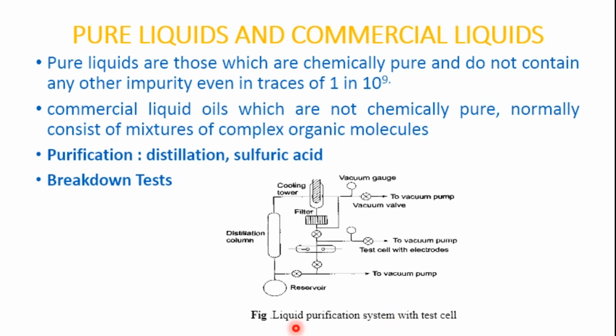The liquid flows from the reservoir through a distillation column where ionic impurities are removed. Then water is removed by drying out or freezing out at low temperature. Then the gases dissolved in the liquid are removed by cooling the tower and pumped out by vacuum pumps. Then it flows to the filter where the dust particles are removed, and the liquid thus purified flows back to the test cell. The vacuum system helps us remove moisture and other gaseous impurities. So this is one example of purification.